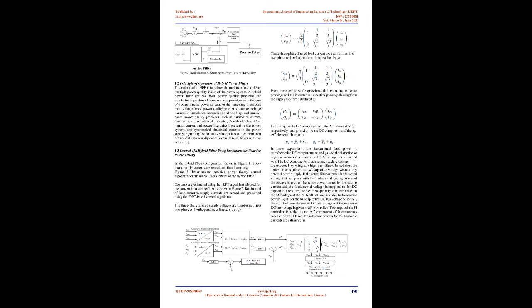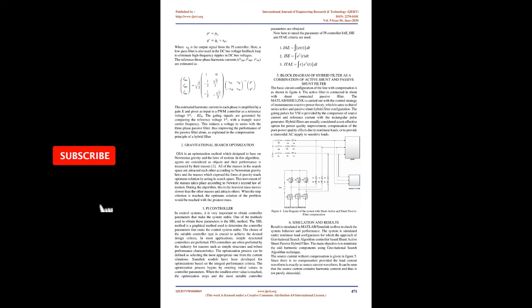If the active filter outputs a fundamental voltage that is in phase with the fundamental leading current of the passive filter, then the active power formed by the leading current and the fundamental voltage is supplied to the DC capacitor. Therefore, the electrical quantity to be controlled in the DC voltage of the AF feedback loop is added to the reactive power, qs. For the buildup of the DC bus voltage of the AF, the error between the sensed DC bus voltage and the reference DC bus voltage is given to a PI controller. The output of the PI controller is added to the AC component of instantaneous reactive power.